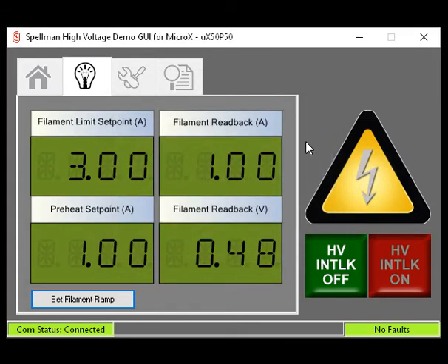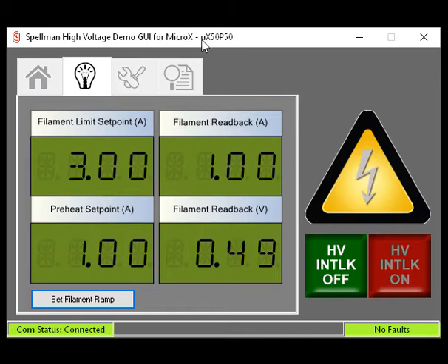This setting is not required, but it may have benefits like a longer filament lifetime. The two remaining displays are the filament readback in amps and the filament readback in volts.